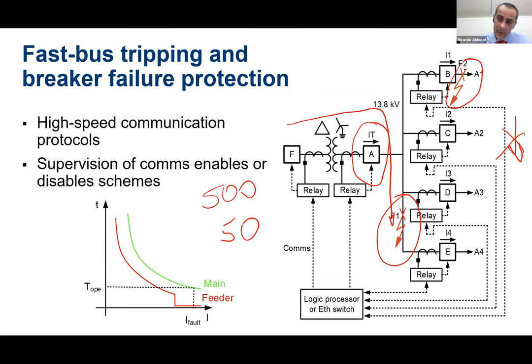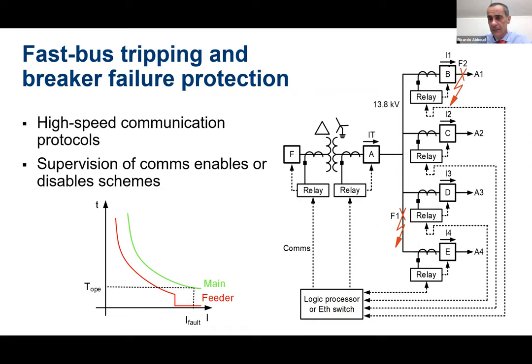Okay. However, when I have a fault in the feeder, it will send the block signal, and the main relay will not trip. If there is a breaker failure, for instance, for a fault in front of the feeder, if the breaker does not open, this relay can send a breaker failure signal to the main relay saying, hey, I sent the trip to the breaker, but the breaker didn't open. Can you please trip your breaker? So the main relay will trip the breaker and clear the fault. So this is the breaker failure with the fast bus tripping using the same communication channel.